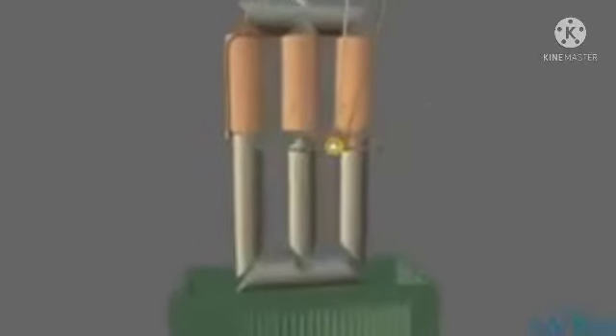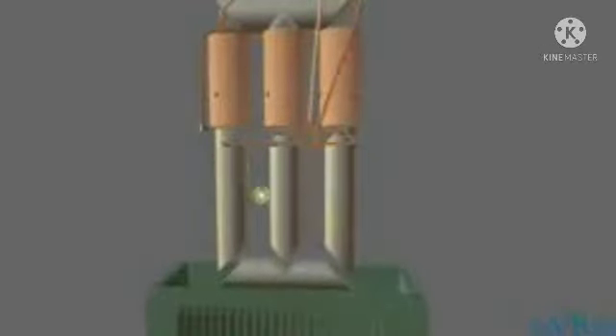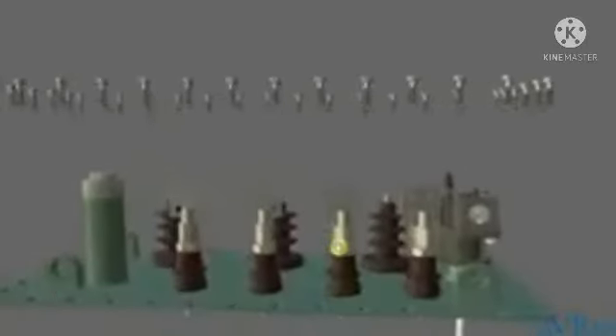Let's break this down into its individual components again, just to have a look, see what is inside the box. And we can see there is our transformer core again, 3 limbs, that's 3 phase. We've got the 2 yokes, one at the bottom, one at the top. Then we have our bushings, and all of that can be assembled again to complete the hermetic type transformer.